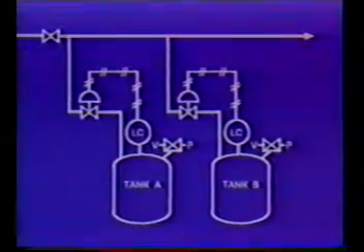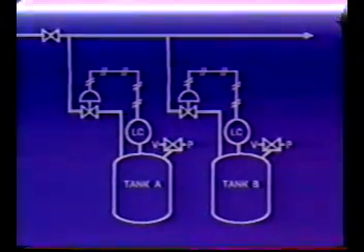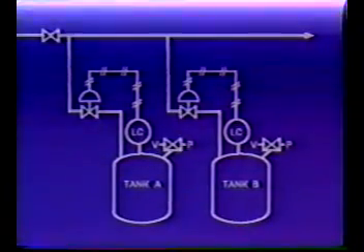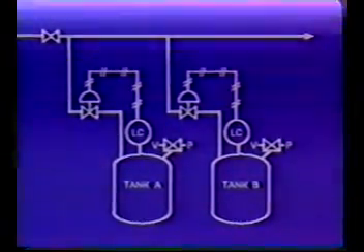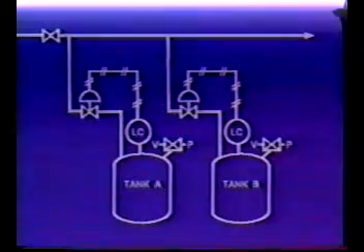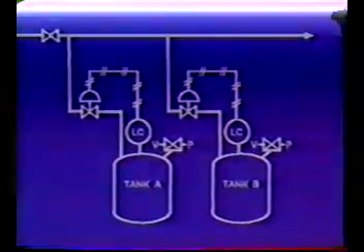Consider this system, where the process fluid is a liquid that contains erosive fines. Steady-state operational conditions result in differential pressures of up to 150 psi. As you can see, globe valves with these trim styles do not meet the system requirements, and therefore they need to be eliminated from the list of suitable valves.